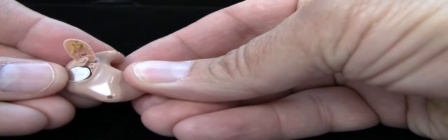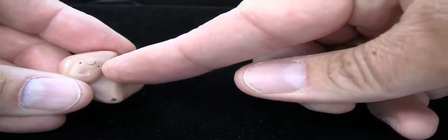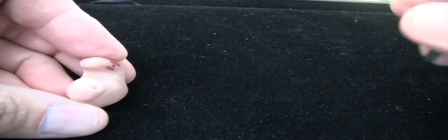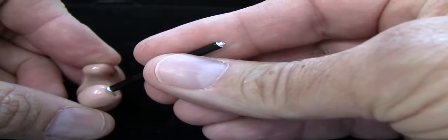For an in-the-ear hearing aid, we're going to check some of the same things. Number one, we're going to check whether there's a new battery in it and if it's inserted correctly. Also, these dots right here are the microphones, and again we will take a dry toothbrush and brush across. And on most in-the-ear hearing aids, you will notice there may be a filter that captures wax, and we will replace that with a tool like this and then put in a new filter.